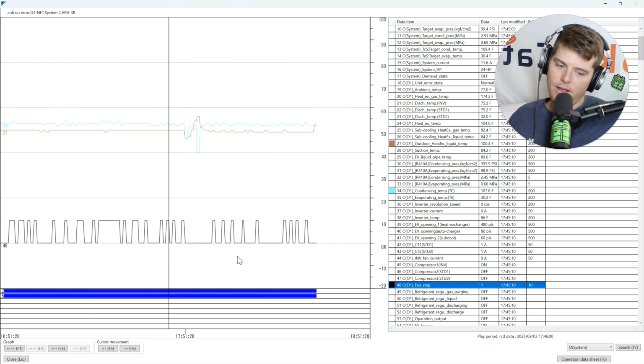Oh, it's overcharged. No. Come to find out, no one set the high fan static setting speed on the unit, and they put snow hoods on it. You have to set the high fan static speed setting on that unit specifically. Because again, when you add ductwork to it, when you restrict the volume of air that can get to the coil, you have to increase the fan speeds. Otherwise, you're going to get insufficient airflow across the coil. That's basic refrigeration. But again, you can't just take one thing and say, when this happens, it's always this.